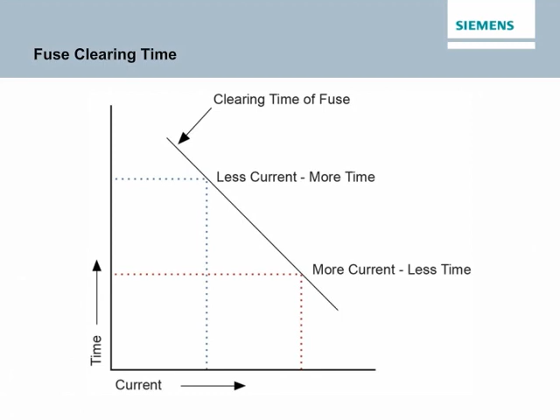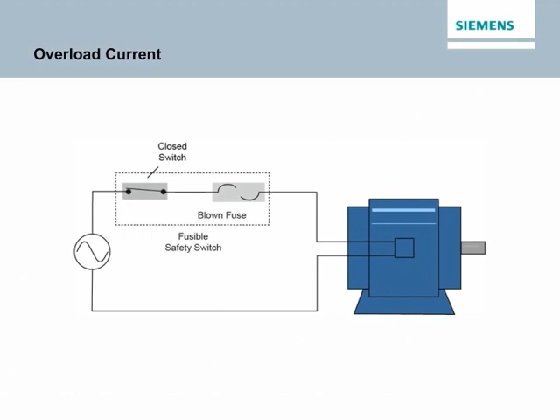The accompanying illustration shows a symbol for an open fuse, commonly referred to as a blown fuse. This is not a legitimate symbol. It's used here for illustrative purposes only. In this example of a motor circuit, an overload has occurred, causing the fuse to open and remove power from the motor. As a result, the motor is stopped even though the switch is closed. Keep in mind that the fuse in the fusible safety switch is sized to protect the conductors that supply the current to the motor. Overload protection for the motor is normally provided separately, often by an overload relay.